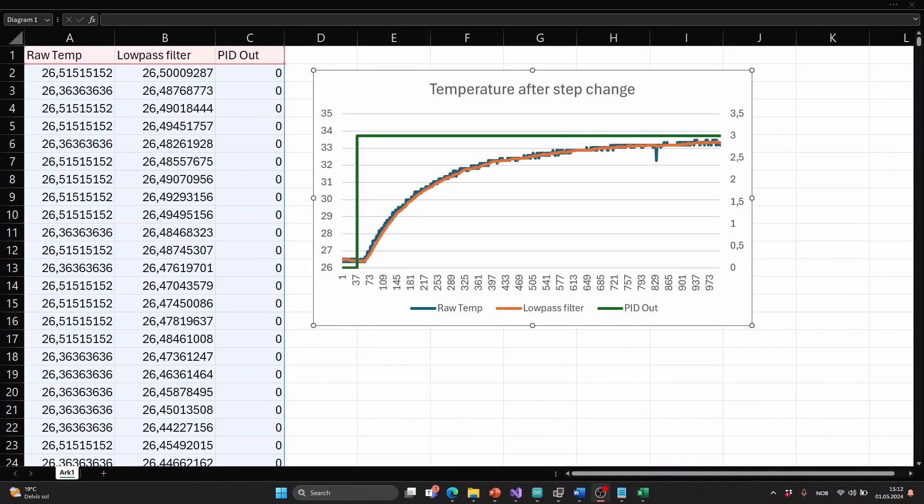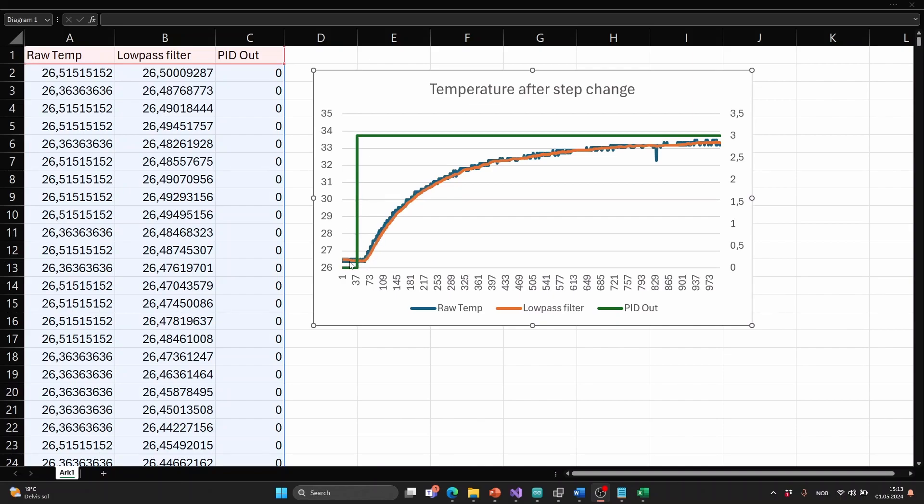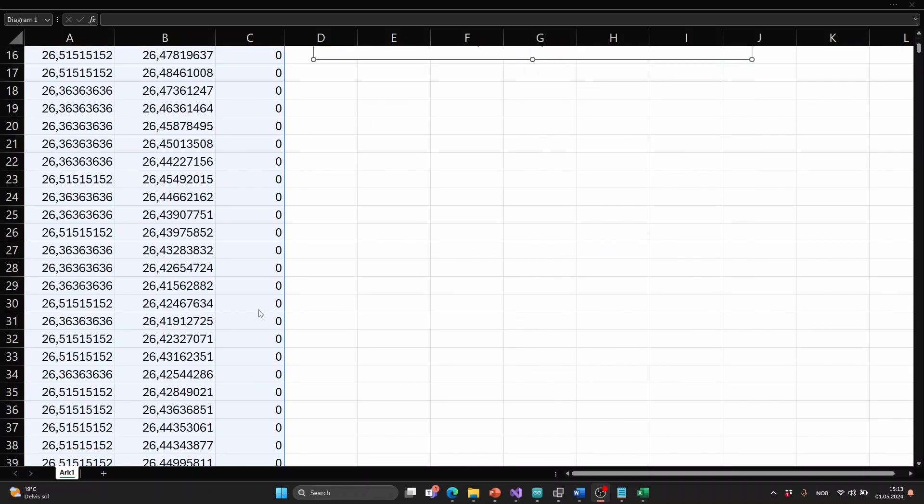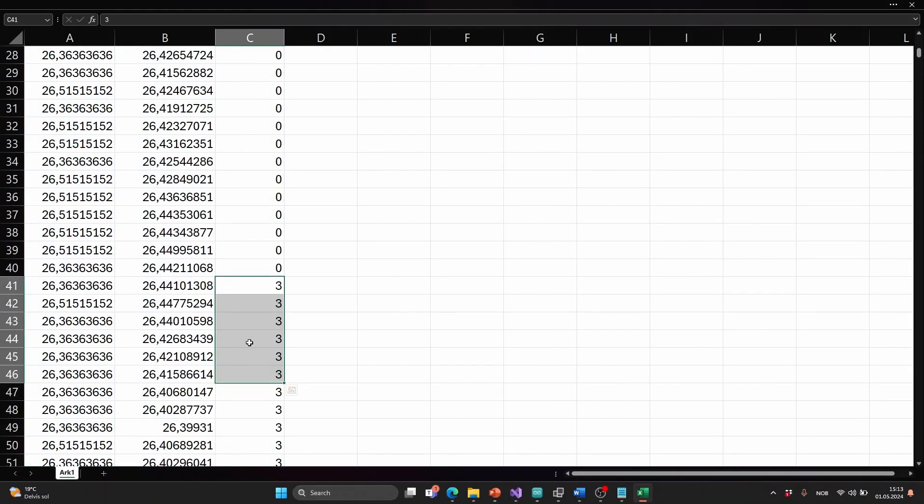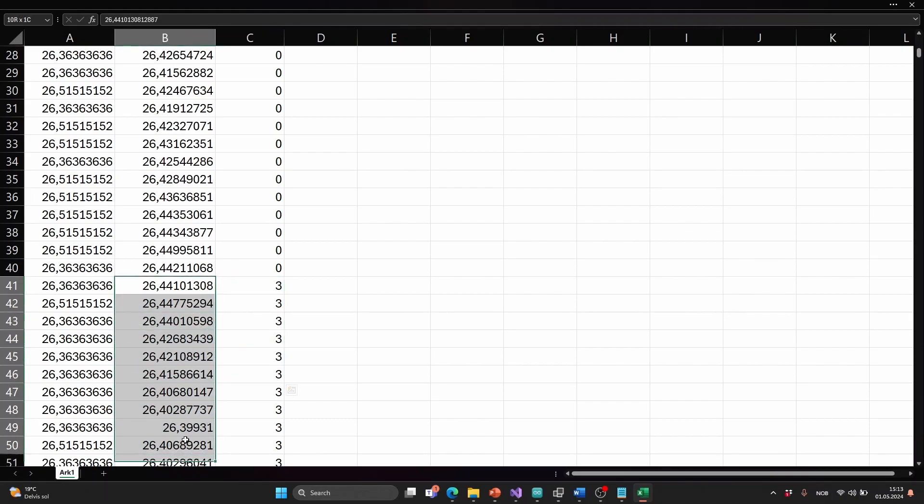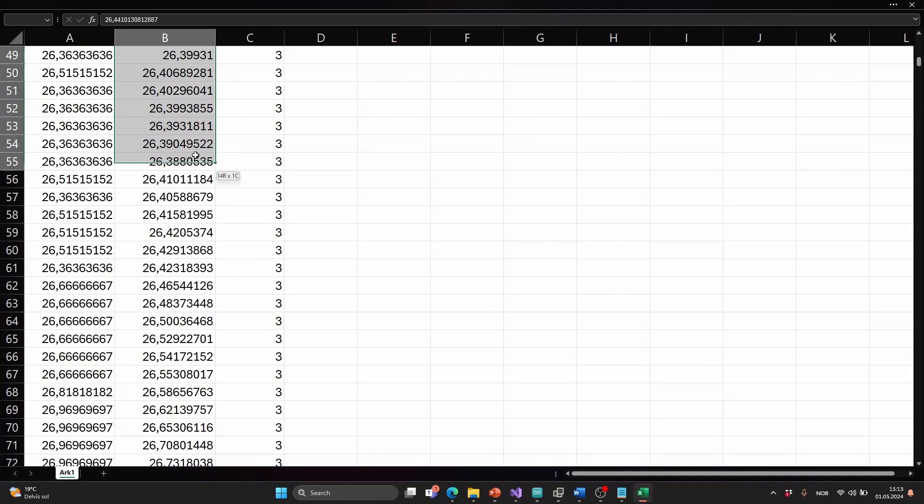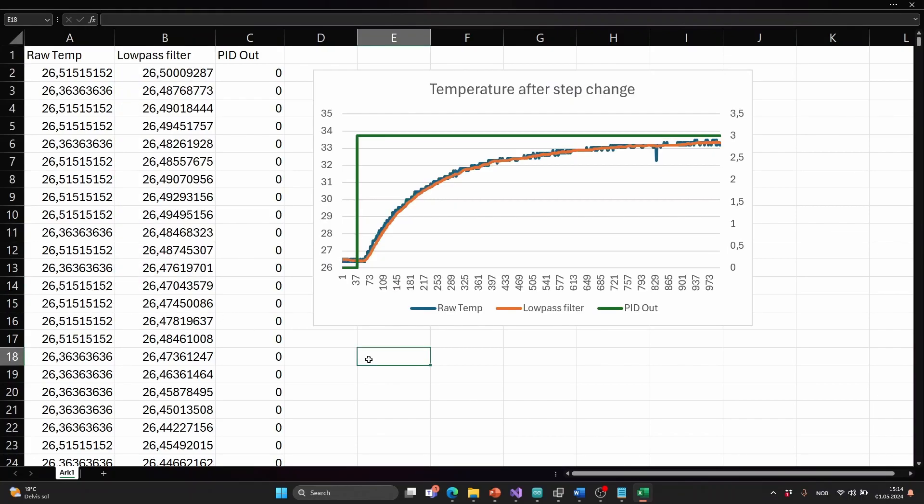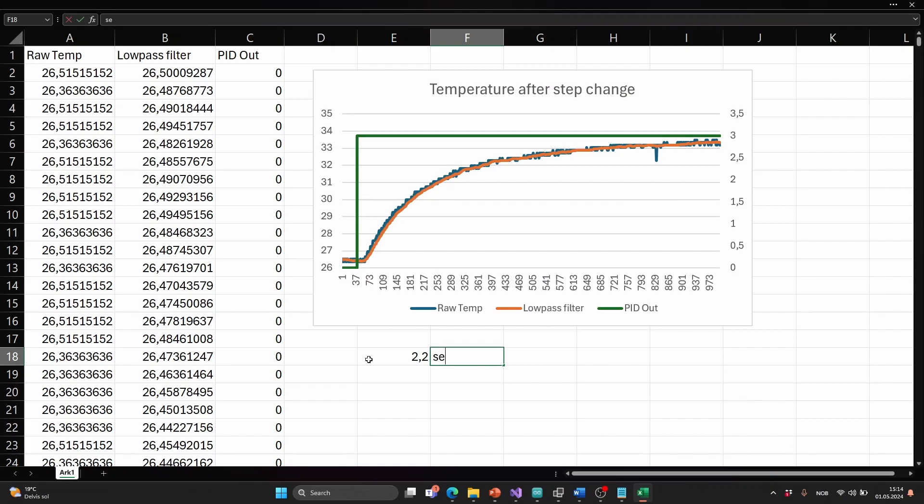The first thing we can do is to find the time delay and we can see from the plot that there is some delay from the time where the output was set to 3 to the time we see something happening. So to find this we can go to the line where the controller output was set on. So now we can count the lines until we see any change in the temperature. And I think that happens around here. So that's 22 cells. And since I know there is 0.1 seconds per cell we can do this simple calculation. 0.1 times 22. So the time delay is 2.2 seconds.